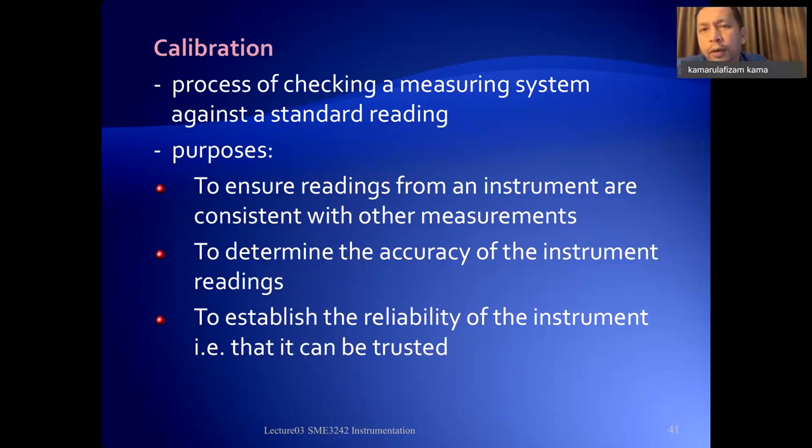This calibration issue, you have mostly with analog sensors. You won't have this kind of issue with digital sensors. That's why, as I mentioned in the previous lecture, we had a lot of analog sensors previously, but recently we have more and more digital sensors because of this issue. Analog sensors give the reading straight away from the input they are sensing and from the conditions of the sensor. The sensors are made of materials, and material properties change over time, and over a long period you may have drift in the reading, so you have to recalibrate to compensate for the error of material deformation or property change. All right.